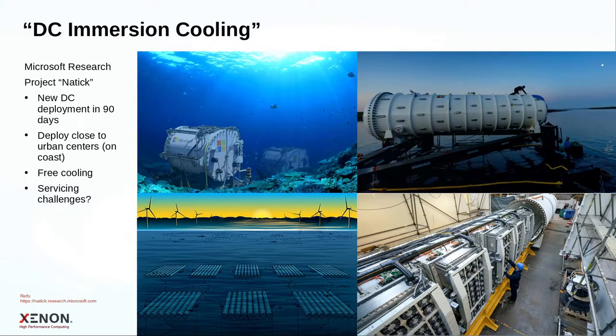They started out with smaller tanks, and recently went to version 2 with a much larger tank. You can see the cylindrical tank in the back, with custom designed server racks with all the HPC equipment in the front. That just slides into the tank, gets hermetically sealed, and you have power and communications in and out somewhere on the side.